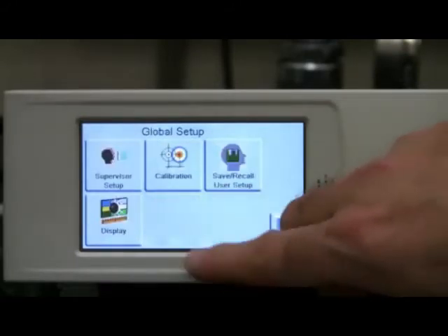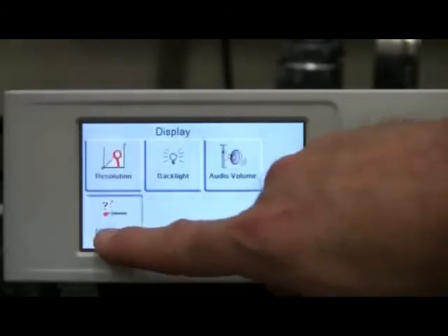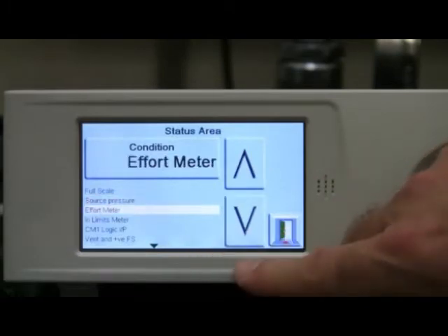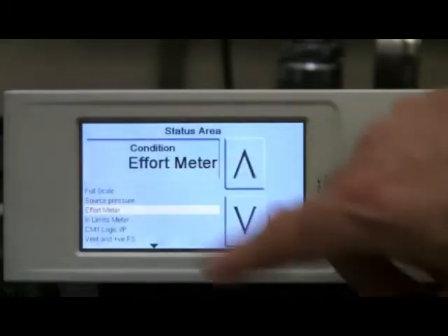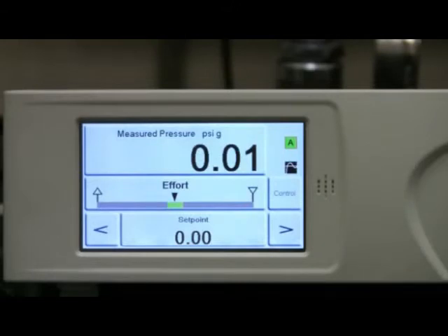Now that the source pressure is set, we will change the center section to display the effort meter, which continuously monitors the activity of the patented pulse width modulated control valves. This will allow us to quickly and easily determine if there is a large leak in our device under test connections. If the effort meter is in the center green section when the set point is reached, all is well. If the effort meter is outside the green area, this is an indication there may be a large leak, which would need to be addressed before proceeding with the calibration.